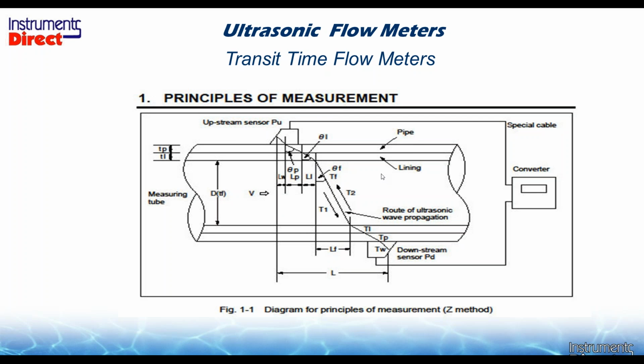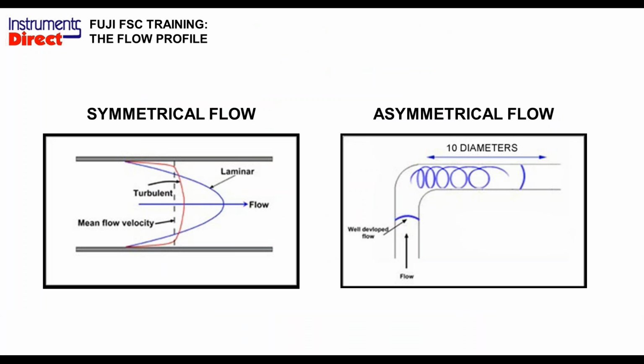Did you ever take a straw and drop it into a glass of water and it looks like it's kind of chopped a little bit? Well, it refracts there. We have to take that into account. We have to take into account the flow profile and the sound speed, out to the other transducer on the other side. Mathematically, we know where the sensor is going to go before we put it on the pipe. In days of yore, all these things could affect the performance of the device, and today we have drop-down menus to compensate for a lot of these things. So hard before, and today the operation manual is a front and back piece of paper.